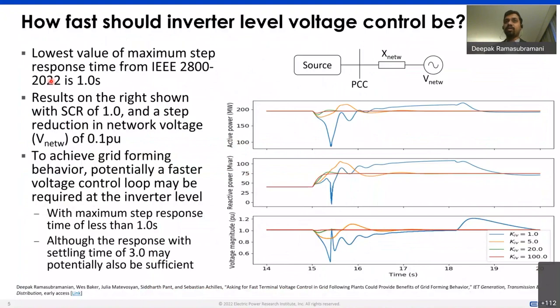And if we take that one step further and compare it with standards like 2800-2022, which is the recent standard approved for bulk power system connected inverter-based resources, and we look at that standard from the perspective of the minimum step response time for voltage that is prescribed, the minimum step response time is 1 second. And if we look at the same kind of results where you have a source connected to a network and you start lowering short circuit strength, at a short circuit strength of 1, with a step reduction of voltage of 0.1 per unit, we start needing to go towards a faster, more robust voltage control loop in order to bring about stability at this low short circuit strength scenario.